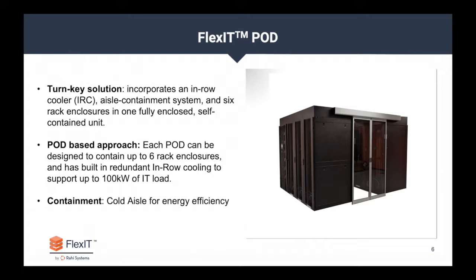The IRC features a unique 900 millimeter chilled water cooler with a capacity to cool up to 100 kW of IT load and run more efficiently than the traditional CRAC units that are typically found within a data center environment.